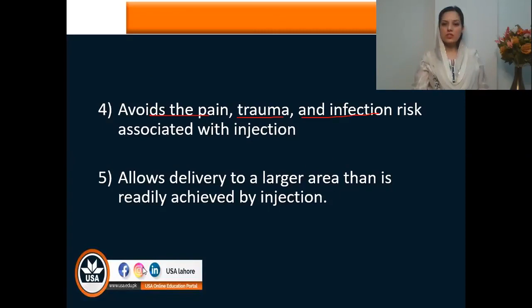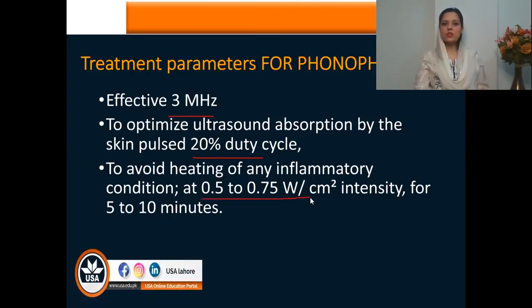Now, what should be the treatment parameters that you are going to use? You can use 1 megahertz and 3 megahertz, but the most effective is 3 megahertz. To optimize ultrasound absorption by the skin, use pulsed mode with a 20% duty cycle, and to avoid heating up and inflammatory conditions, we may use an intensity of 0.5 to 0.75 watts per centimeter squared for 5 to 10 minutes.